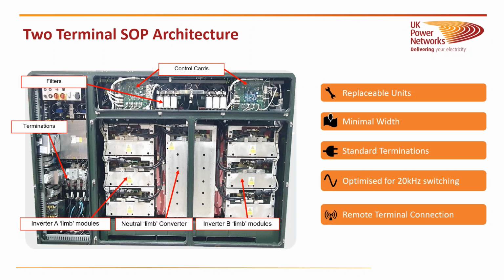So I'm going to take you through some of the key points about the architecture of the SOPs and the SBB, and then some of the important things we've had to consider when installing these. So here on the first slide, this is the 2-terminal SOP. This has just been built in the TPS factory, and they're currently testing it at the moment. So what you can see here is a back-to-back converter. It's connected to 2 LV feeders. So you've got an inverter for feeder A on the left, an inverter for feeder B on the right, and then you've got a neutral converter in the middle.